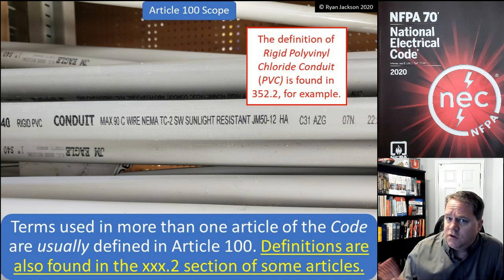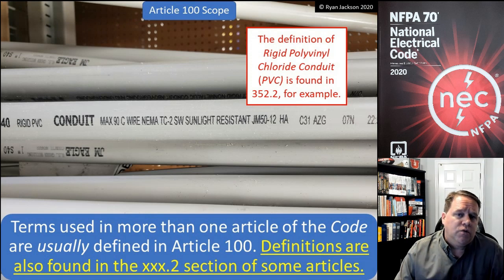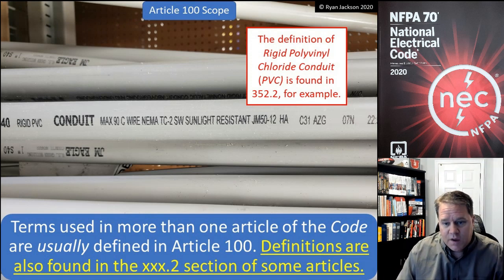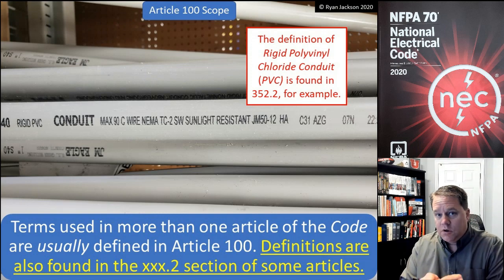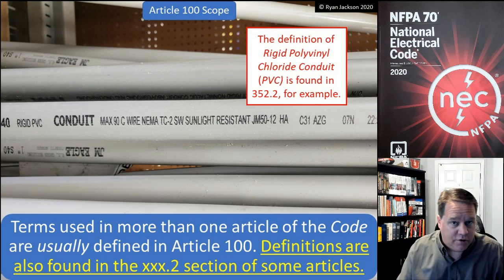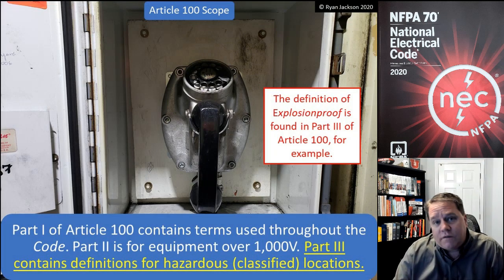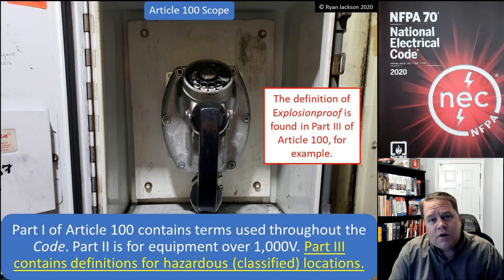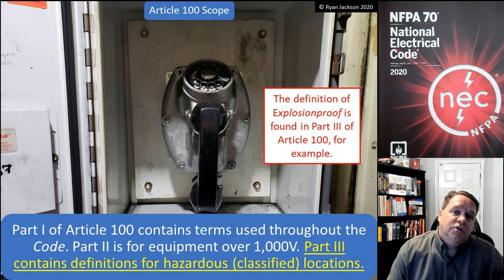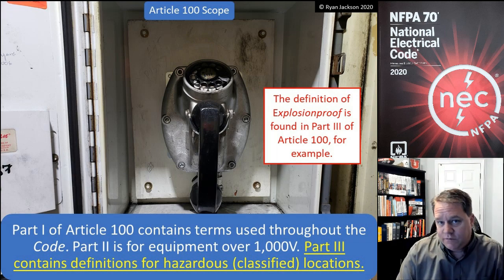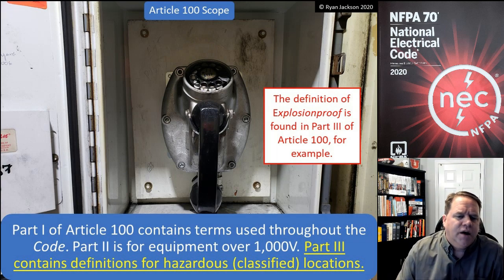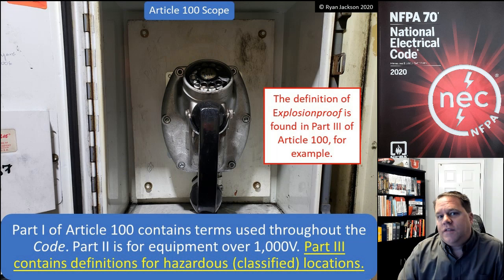They're going to change this in 2023. For right now, just know that if a term is used in more than one article, we define it in Article 100 for the most part; if it's only used in one article, we define it in that article. Part one of Article 100 contains definitions of terms used throughout the code. Part two is for terms used only above 1,000 volts — there are only about six or seven of them.